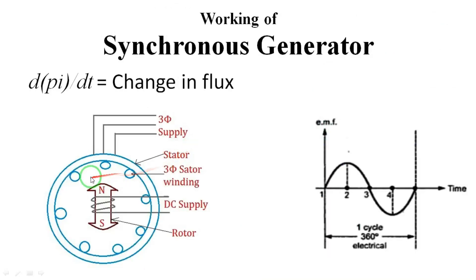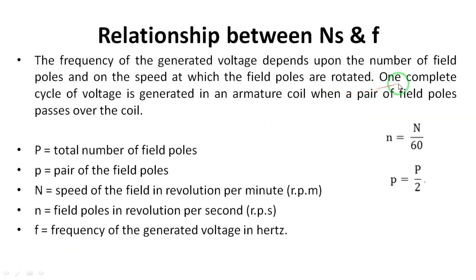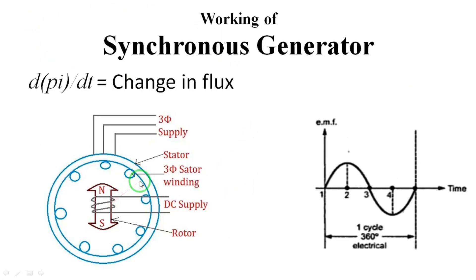One pair of poles means one north pole and one south pole combination. When this one pair rotates 360 degrees, one cycle is generated. If the rotor has two pairs of poles — another north pole and another south pole — then two cycles are generated per revolution. So in one revolution, the number of cycles depends on how many pairs of poles pass over the armature coil.